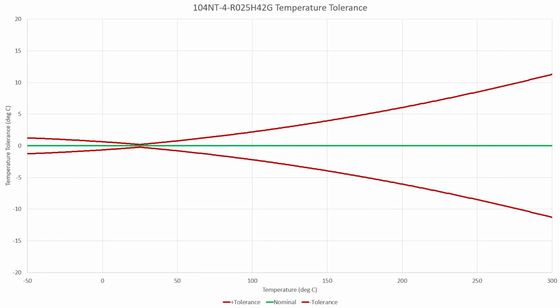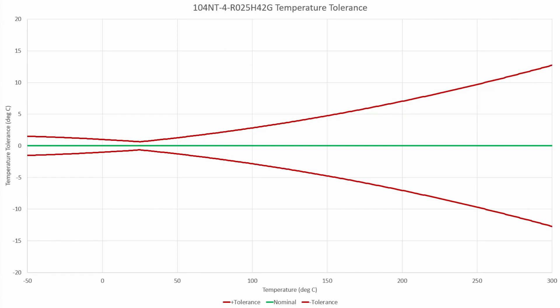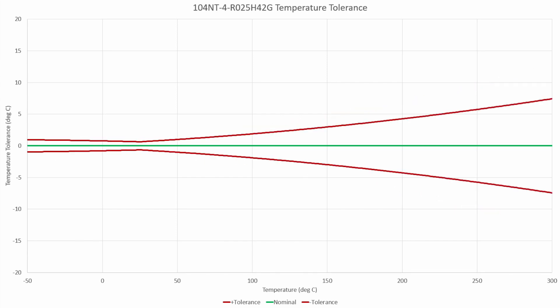Changing the resistance tolerance back to 3% and the beta tolerance from 2% to 1%, the uncertainty around the 25 degrees Celsius mark really didn't change at all. But then out at 300 degrees Celsius, we've improved quite a bit — from 13 to plus or minus 7 degrees Celsius.